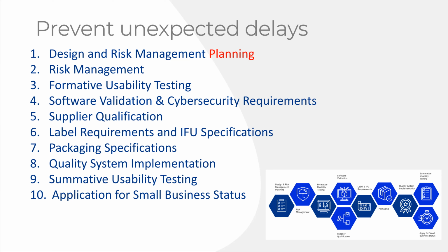The FDA has this 2016 guidance on how to do usability testing or human factors testing, and they talk about doing an FMEA or doing a fault tree in there. But when you get the deficiency letter from the FDA, they want you to use a use-related risk analysis, and they don't want you to estimate the probability of occurrence of harm when you're doing use-related risks. They want you to assume that the risk will happen. So they're actually going against or contradicting exactly what's in their own guidance document.